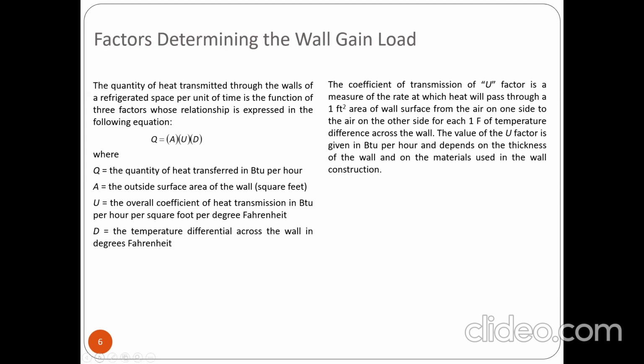The coefficient of transmission or U factor is a measure of the rate at which heat will pass to a 1 square foot area of wall surface from the air on one side to the air on the other side for each 1 degree Fahrenheit of temperature difference across the wall. The value of the U factor is given in BTU per hour and depends on the thickness of the wall and on the material used in the wall.